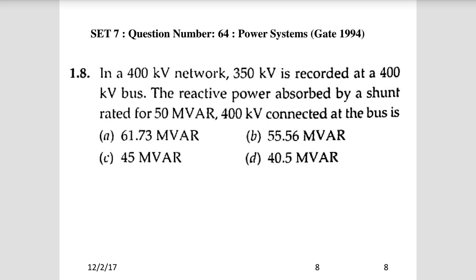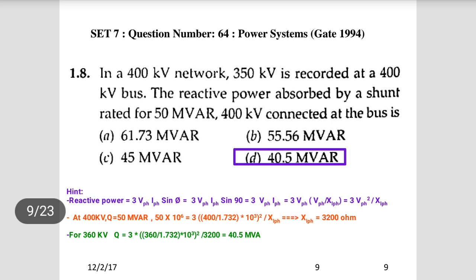To find the answer, we use: reactive power Q = 3 × V_phase² / X_phase. For 400 KV the rated Q is 50 MVAr, so we can calculate the reactance X = 3200 ohms. Substituting X = 3200 ohms with the actual voltage of 350 KV, we get Q = 40.5 MVAr.